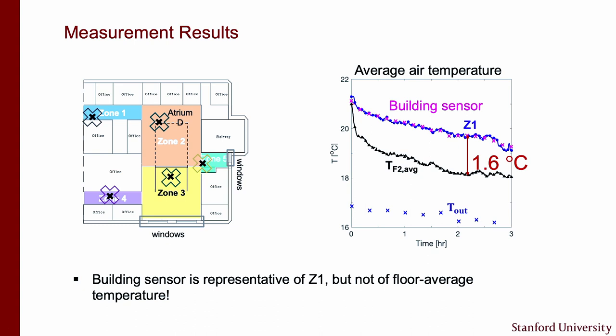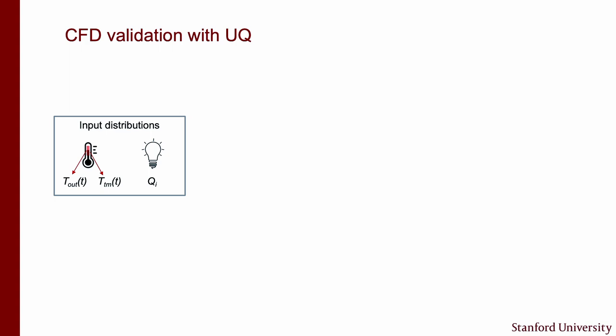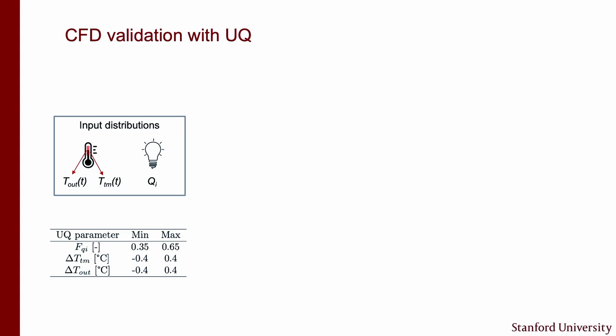Okay, so now with our new measurements we can go back and try to validate our CFD. We again do an uncertainty quantification process because when we run the CFD simulation we have to specify an outdoor temperature, and there's uncertainty on that measurement. We also have to specify the thermal mass temperatures, and there's uncertainty on those as well. And then the internal loads is something else we have to put into the CFD model, so that's also uncertain.